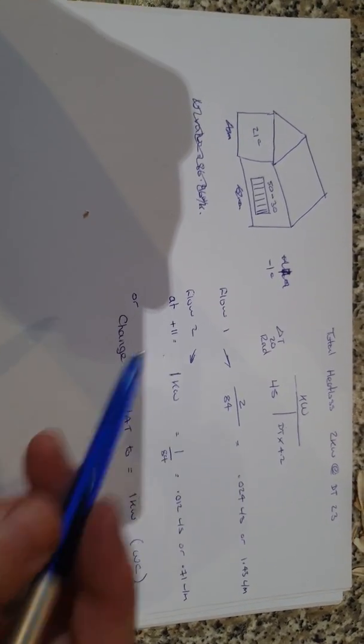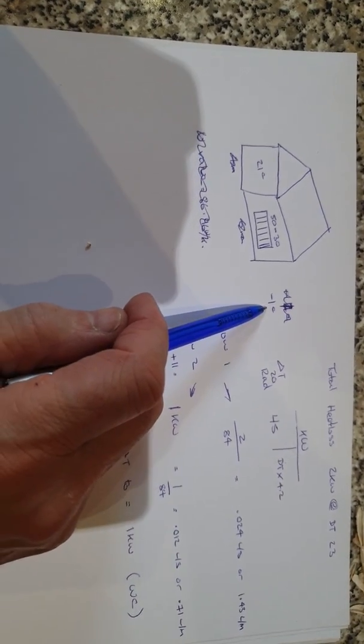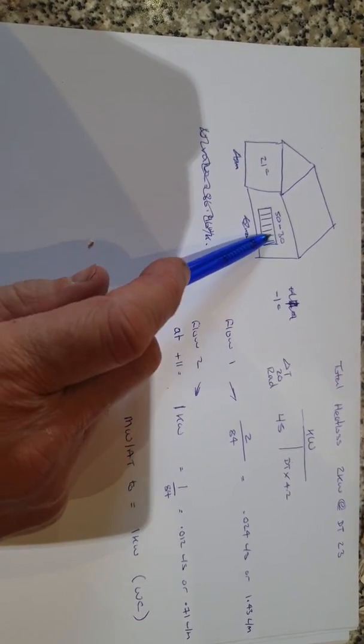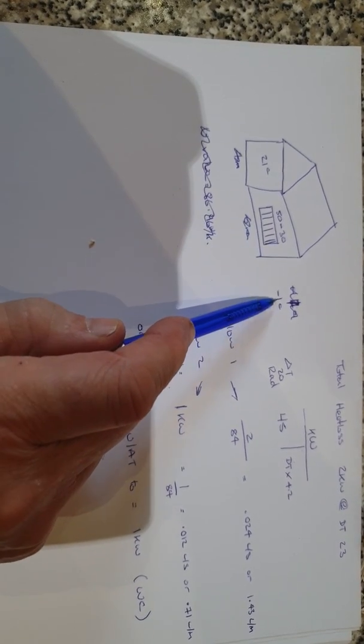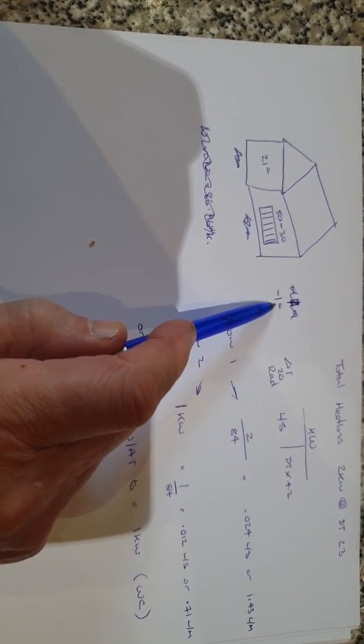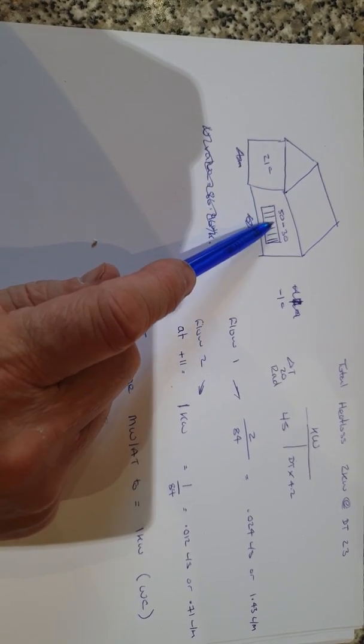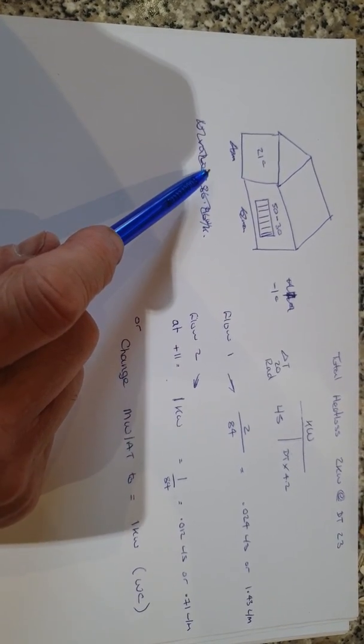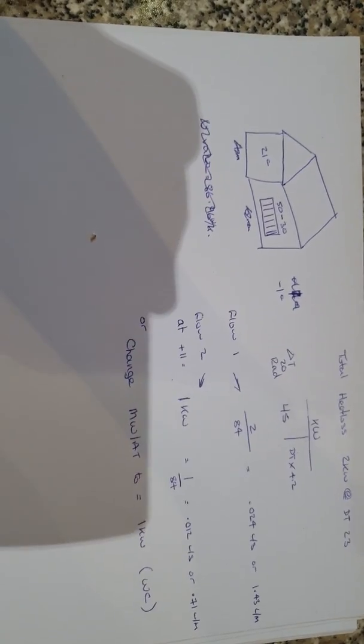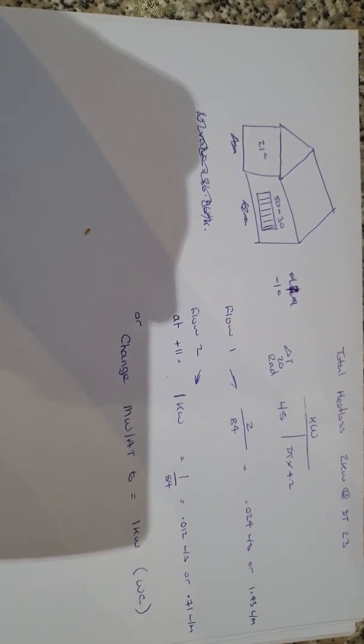I hope that explains it. The basic principle is if you're going to balance and set your flow rates based on delta T 20 when it's not your design temperature outside, based on it being the correct temperature inside, you're not going to balance that system correctly. You're going to be throttling that down and strangling it. It's not going to perform properly. You'll have much wider delta Ts when you're at design temperatures than you were meant to.